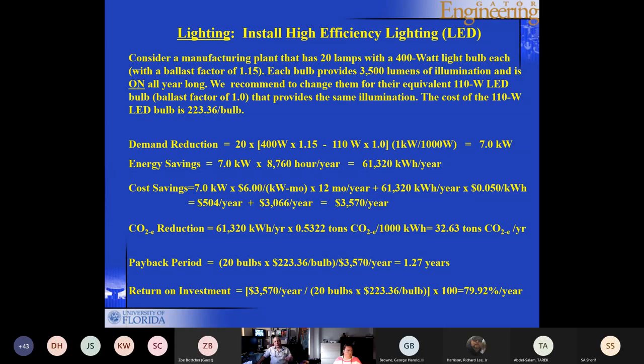But when you compute the cost savings that you're going to achieve, you're going to factor in the demand cost, which now you're paying $6 per kilowatt for the demand. So if you save 7 kilowatts, that means you're going to save 7 times 6, and then you multiply that by 12 months per year. And then you add that to the savings that you achieve from the 61,320 kilowatt hours per year that you are no longer expending, times the cost of energy, which is $0.05 per kilowatt hour, and you end up with $3,570 per year of savings.